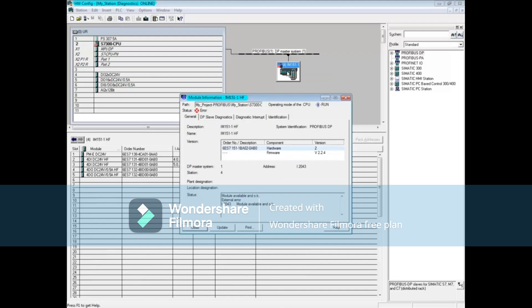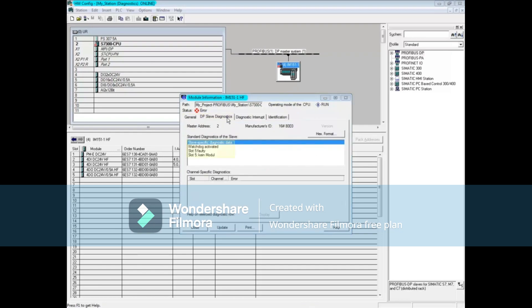The general tab says the interface module is okay, but there is an external error. Click the DP slave diagnostics tab. Here there's slave-specific diagnostic data. In particular, slot 5 is faulty.